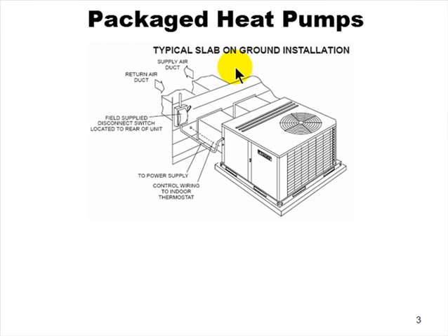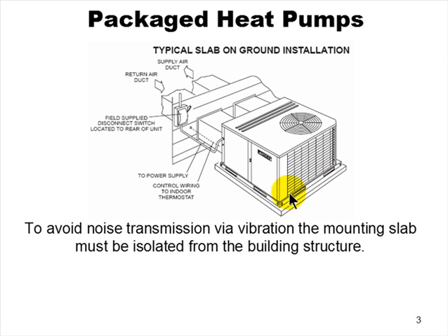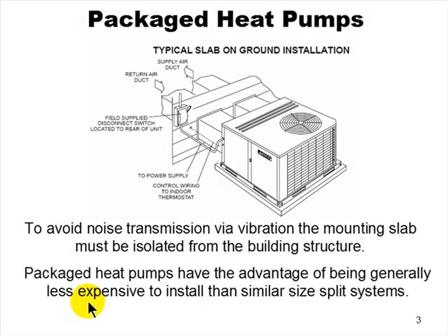Packaged heat pump. Here's a packaged heat pump on the ground, right? Here's a commercial building here, or maybe it's a residence, whatever. But you mount it on a slab. Make darn sure that slab is isolated from the building so it doesn't transfer the vibration and the noise to the building. Now here, with the ductwork, it's fairly rigidly attached, so you need to have flexible connections at some point so that this doesn't transmit the noise directly to the house.